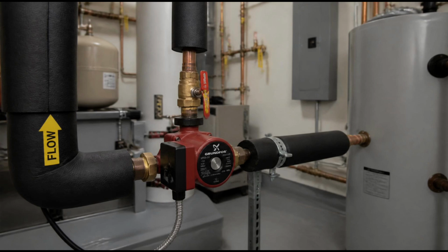The goal is not to push water through the loop quickly, but simply to keep it moving enough to maintain temperature. Variable speed controls allow the pump to adjust its output based on conditions, and in some buildings, timers or temperature sensors modify when and how hard the pump runs. During overnight hours, when demand is low and less heat is being lost from pipes, the pump may slow or pause entirely. During the busy morning hours, it runs steadily to keep hot water available at every tap.